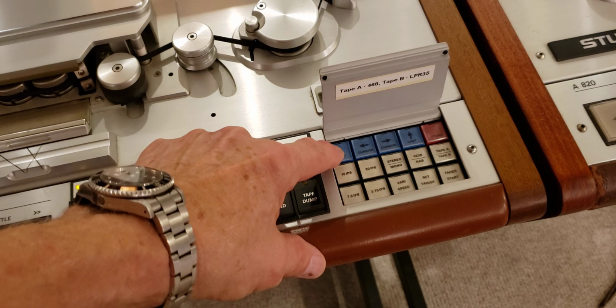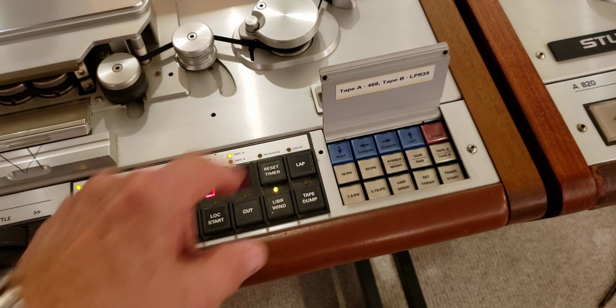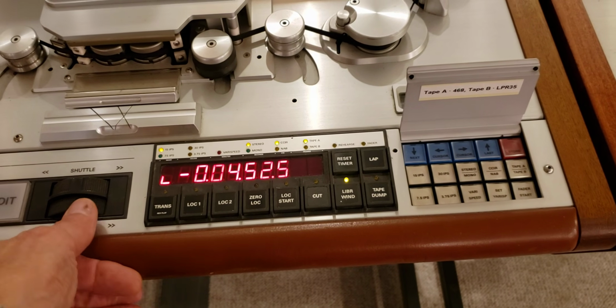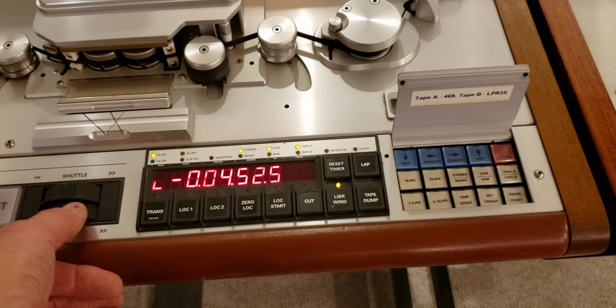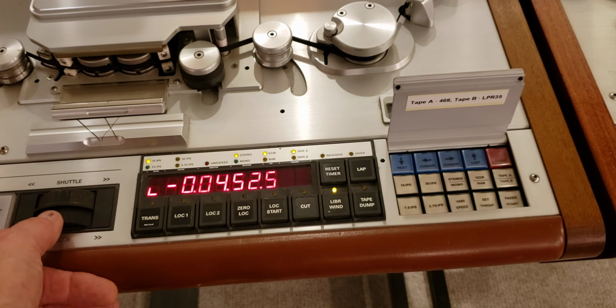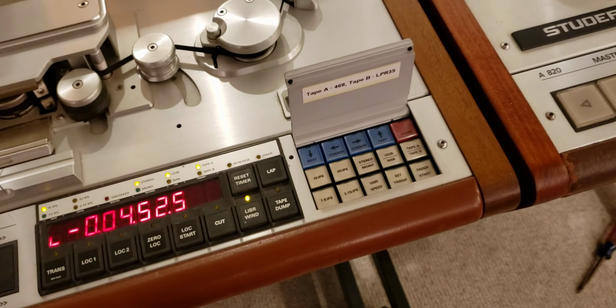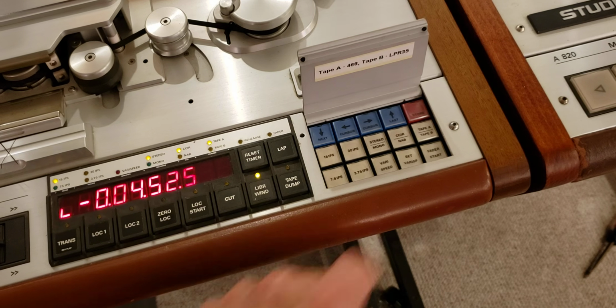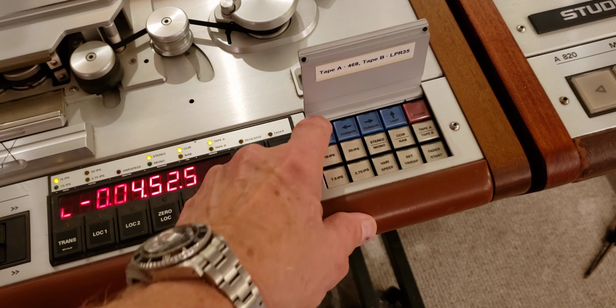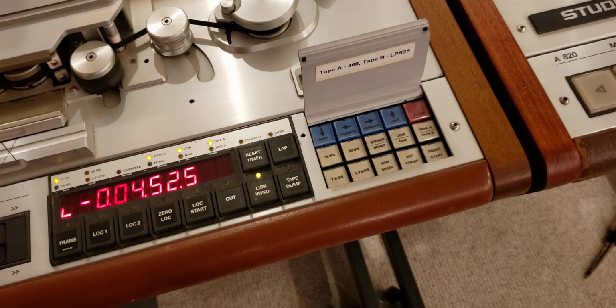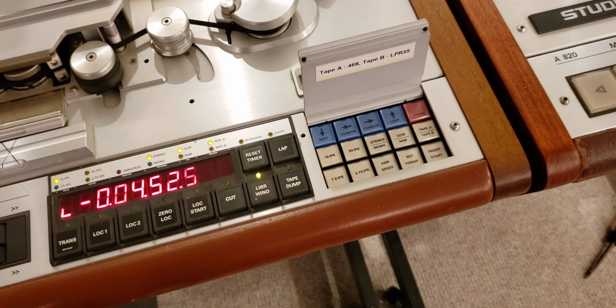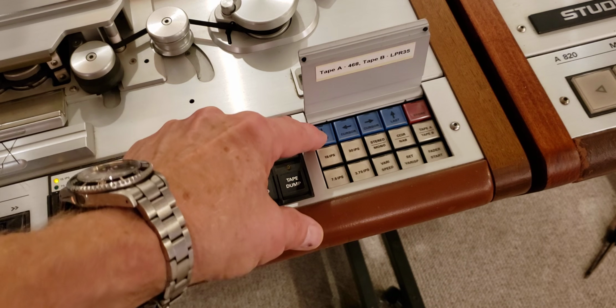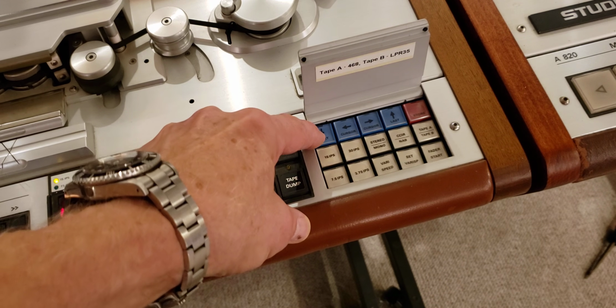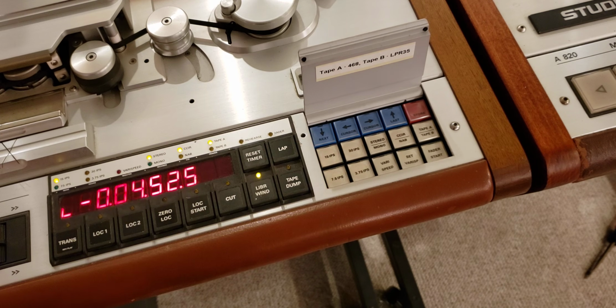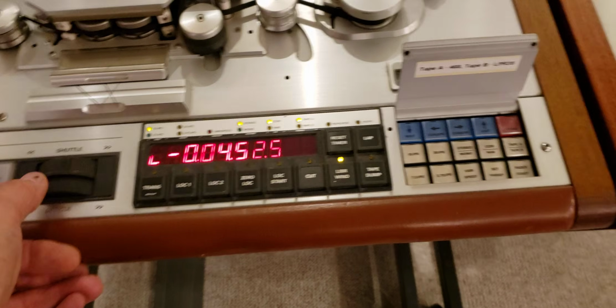You go through the calibration tree using those navigation keys, and you adjust your parameter using this wheel, which is a very, very big joy to operate. It's smooth, it works precisely, it's very predictable. Once you select a particular combination, you simply save it by pressing this button, and then you go further down the menu tree. So the audio calibration is done very straightforwardly. It's very easy. Using this button, you go down from playback level to playback EQ to recording functions, and every time you use your wheel here to adjust the parameter.